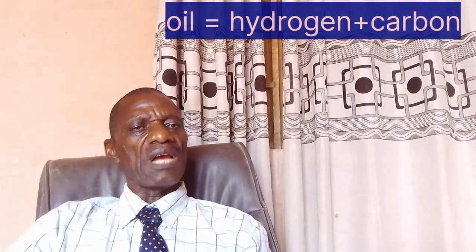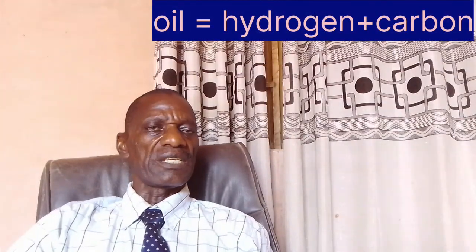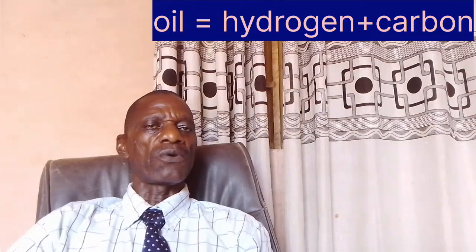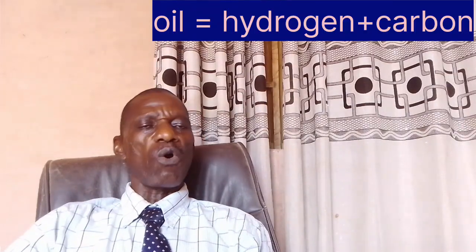It's an oil that has hydrocarbons. And in the course of time, during the arcing and opening, the hydrogen and the carbon disintegrate. They break into hydrogen and carbon. So there will be accumulation of gases inside the circuit breaker, and also there will be carbon deposit.